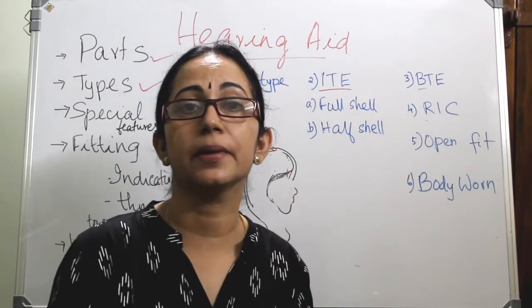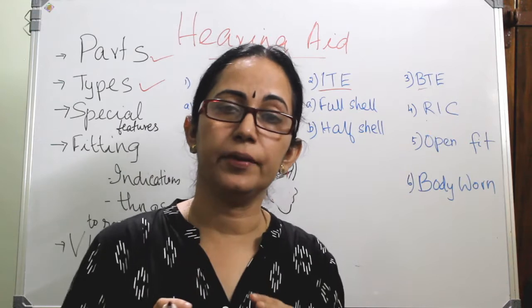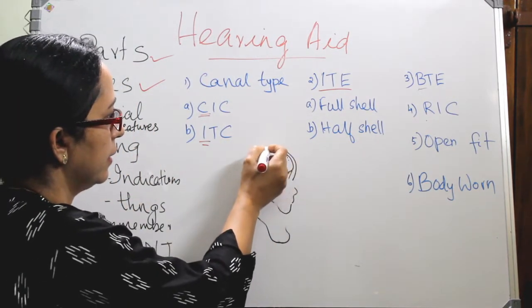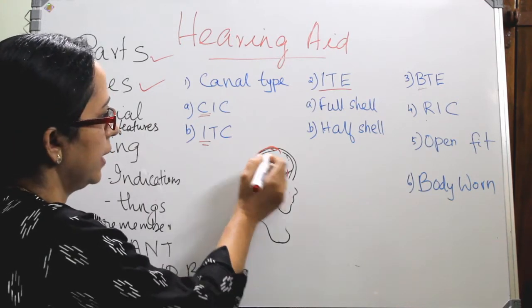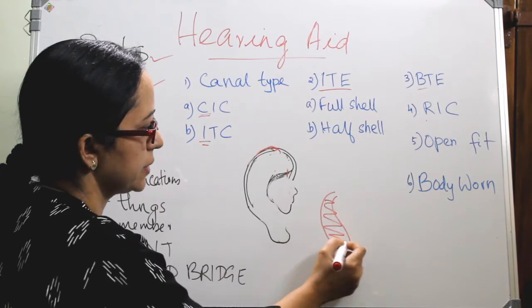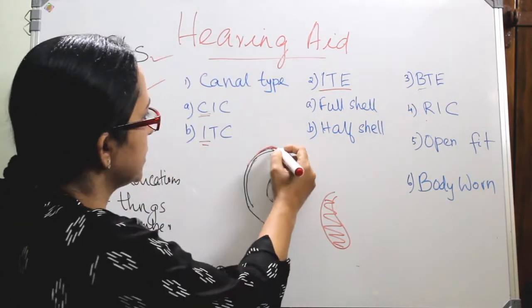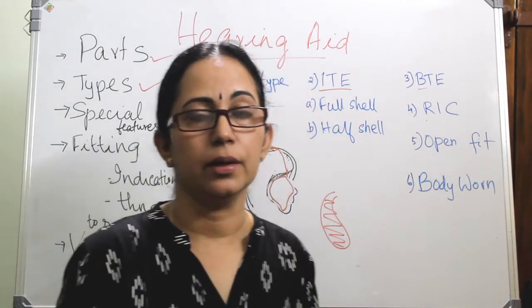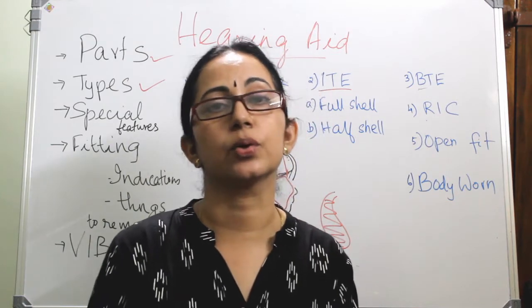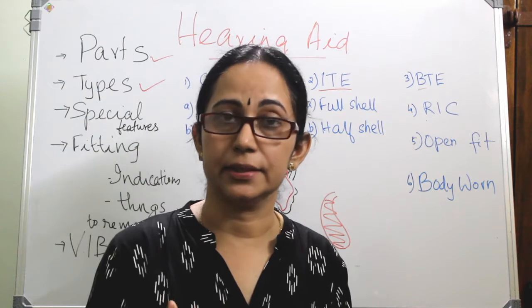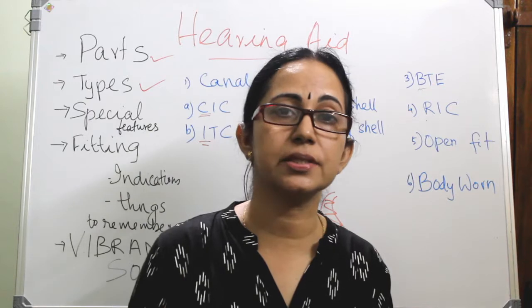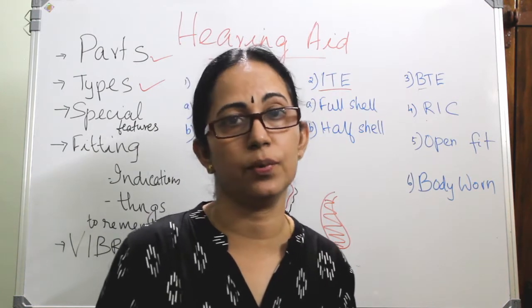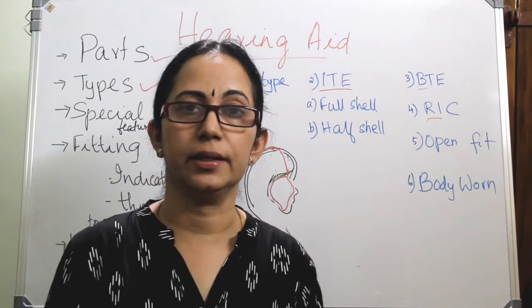BTE (behind the ear) has the microphone, amplifier, speaker, and battery unit in a single piece hooked on the helix, connected to the ear canal via a small wire or plastic tube. It is appropriate for all ages and all types of hearing loss. It is larger than canal types but easier to manipulate. The main disadvantage is that it picks up wind noise.